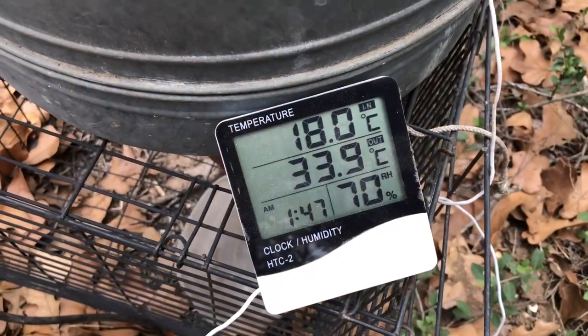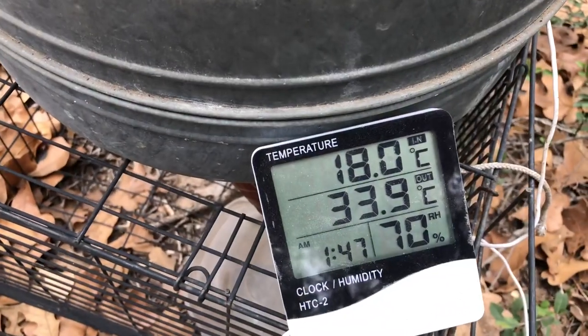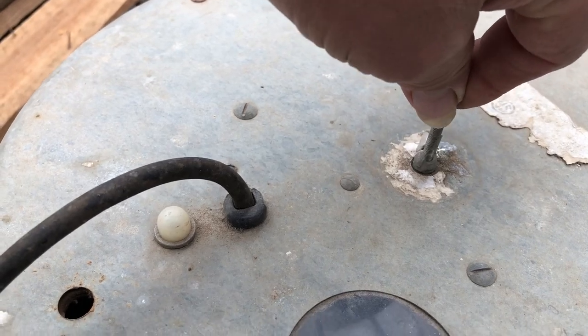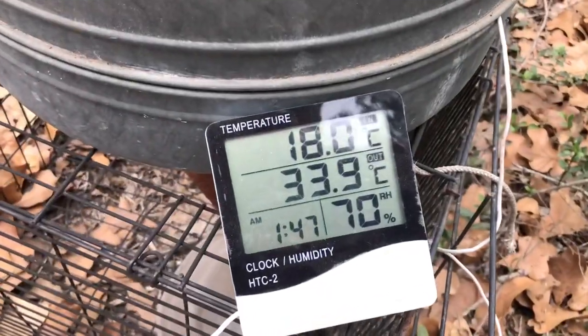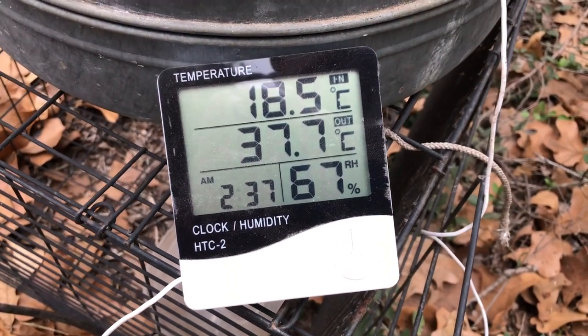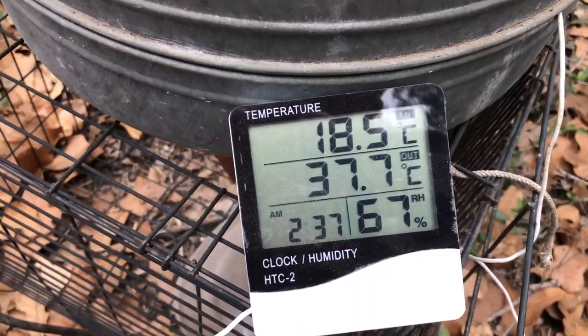It started at 15 degrees Celsius and now it's up to 33, and the light went off again. We're looking for maybe 37.5 to 38 degrees Celsius. So I'll spin this again until the light comes on, then leave it and see if that 33 goes up to 37.5 to 38 — that's 100.4 degrees Fahrenheit.